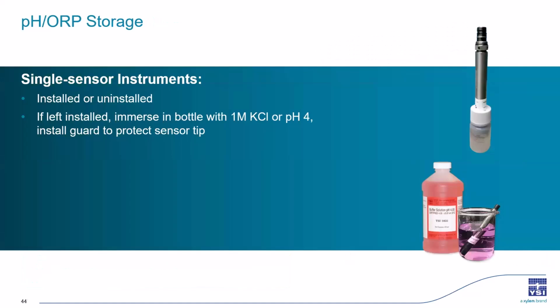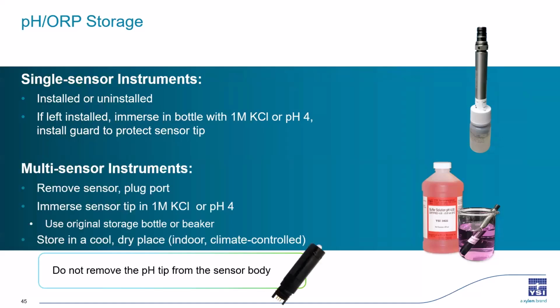So after you've done the proper care for your pH sensor, you can now go ahead and store it. If you have a single sensor instrument with just pH, you can leave the sensor installed or remove it. Either way, you're going to immerse it in a bottle with storage solution, which could either be 1 molar potassium chloride or pH 4 buffer. And we do recommend that you leave the sensor guard on to protect that bulb.